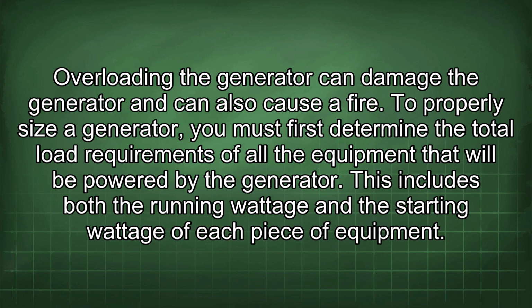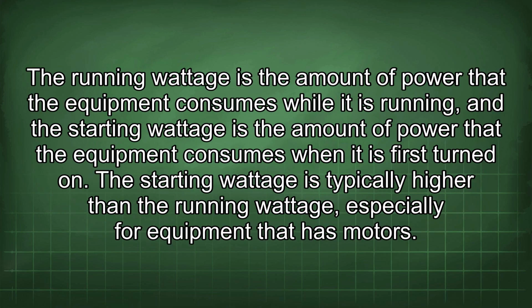To properly size a generator, you must first determine the total load requirements of all the equipment that will be powered by the generator. This includes both the running wattage and the starting wattage of each piece of equipment. The running wattage is the amount of power that the equipment consumes while it is running, and the starting wattage is the amount of power that the equipment consumes when it is first turned on. The starting wattage is typically higher than the running wattage, especially for equipment that has motors.